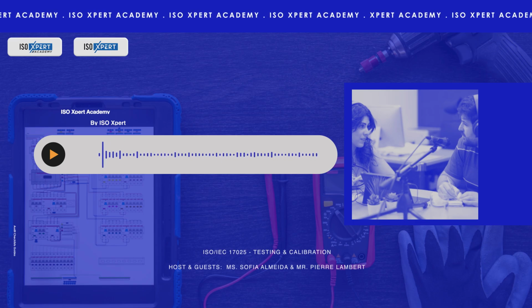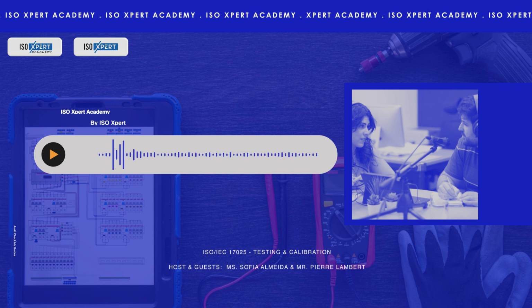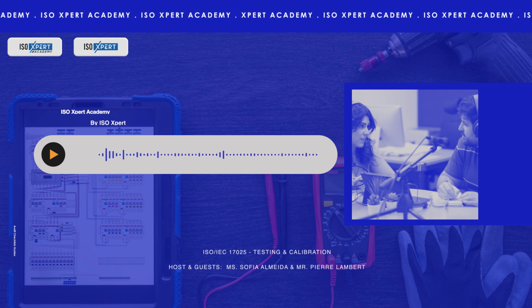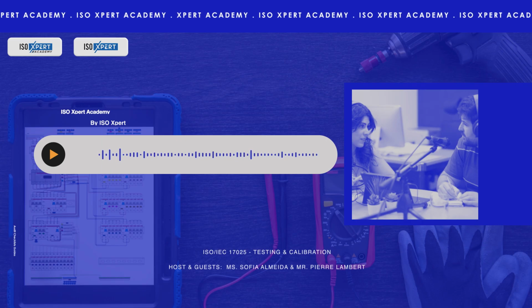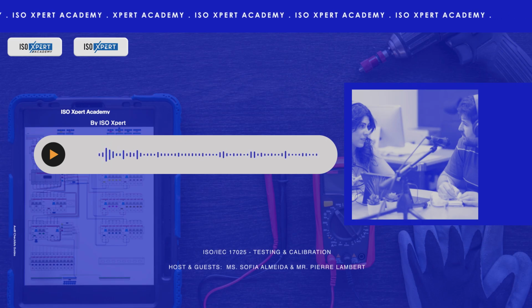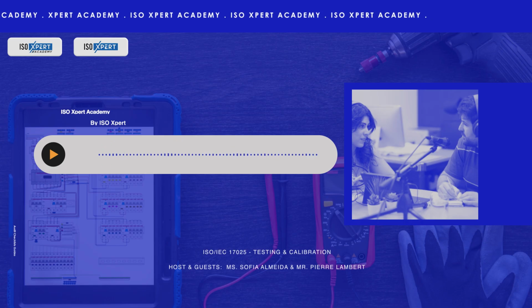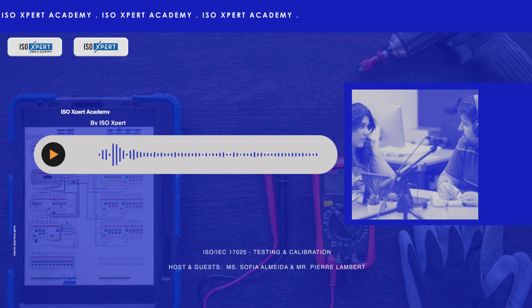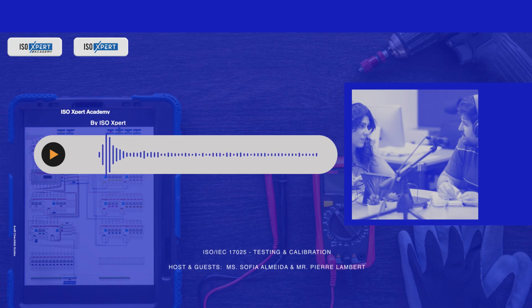What does it typically include? It clearly identifies the NCR with a unique number. It states the specific clause of the standard, like clause 7.5.1, that wasn't met. It gives a precise observation of what the auditor saw or found that was wrong, and the objective evidence supporting that observation. Crucial. It also usually notes the severity. Is this a minor issue or a major systemic problem? And critically, there's space for the lab to document the corrective action they plan to take or have taken, and its current status: is it open, in progress, closed? It provides that structured, actionable way to address issues and continuously drive the lab towards higher standards.